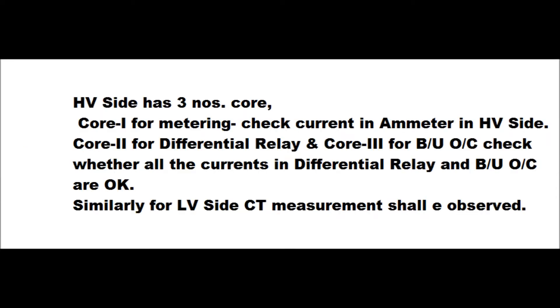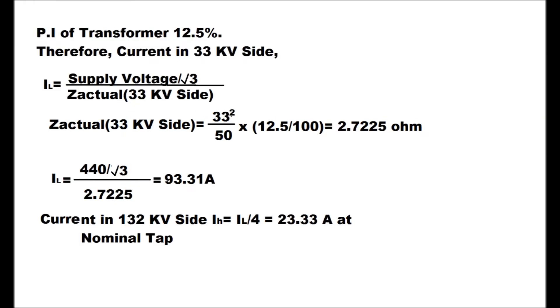For the stability test, the HV Side CT has three cores. Core 1 is taken for metering — check all ammeter currents on the panel side. Core 2 is taken for the differential relay and Core 3 for backup overcurrent — check all currents in the differential relay and backup overcurrent. Similarly, LV Side CT measurements are taken in the ammeter and backup overcurrent and differential relay.